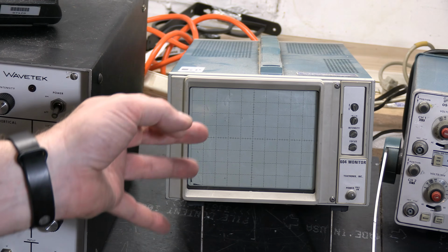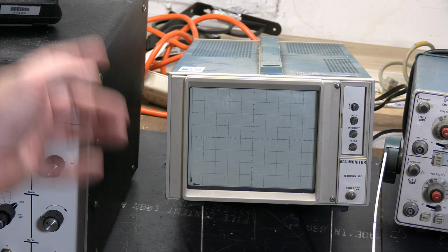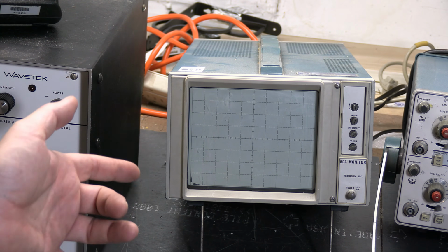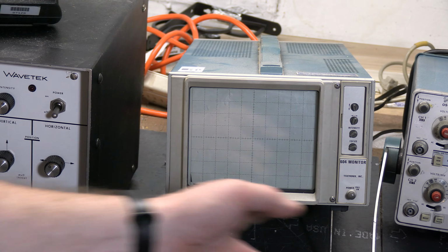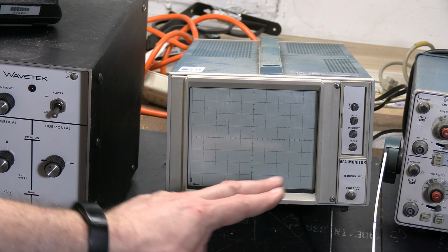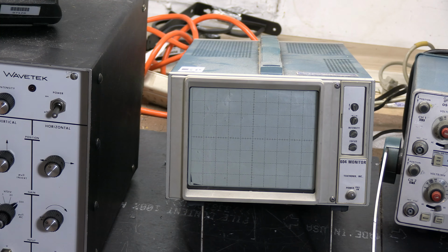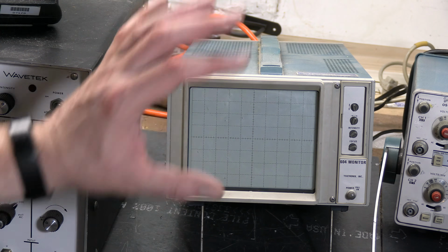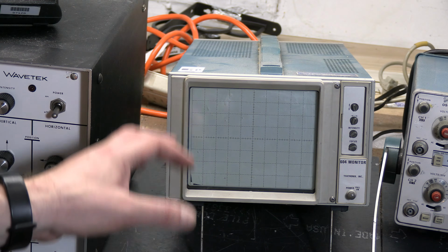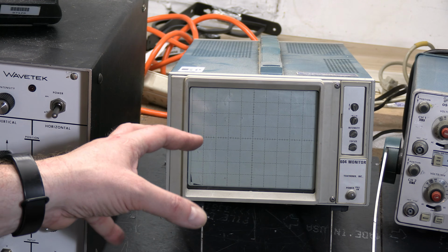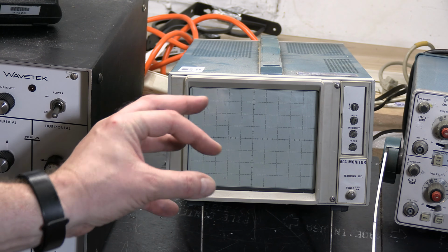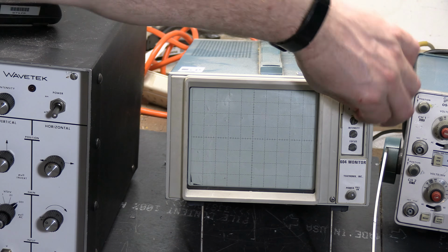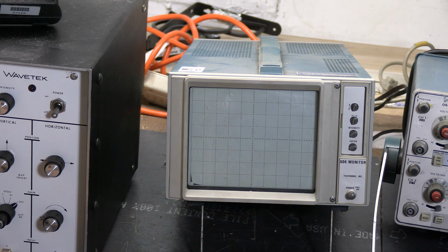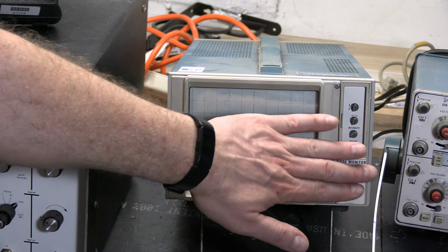Well, on the back there are 3 BNC connectors for X and Y and Z. X controls the beam movement this way, Y this way, and Z the brightness. So it has no sweep, no triggering, no time base, no vertical attenuator. It's up to you to feed in signals that make sense. You only have controls to center it vertically, horizontally, control the intensity and focus. That's all you get on front.